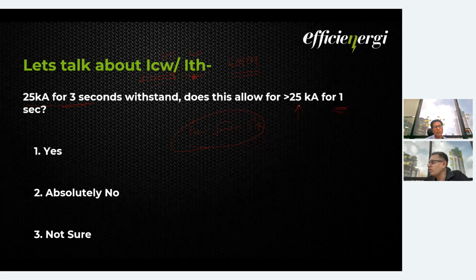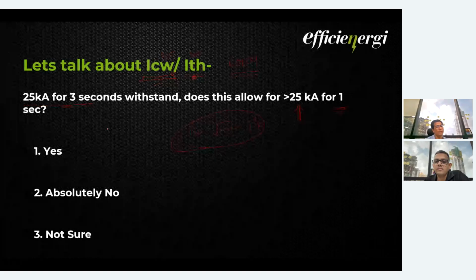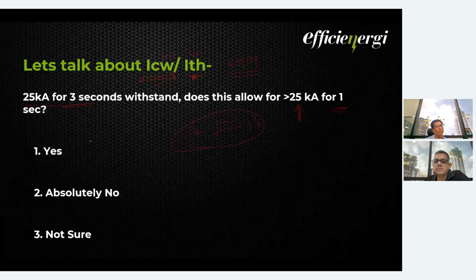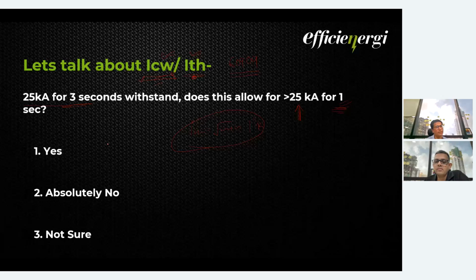I mean, you have a fault. Let's say my breaker manufacturer says 25 kiloampere for 3 seconds by ICW, but unfortunately I have selected a breaker of lesser capacity. The fault at this particular bus is, let's say, 35 kiloampere, but my breaker manufacturer says that we are clearing the fault in 1 second only. We are not waiting for 3 seconds. So can I pass this breaker for 35 kiloampere then?